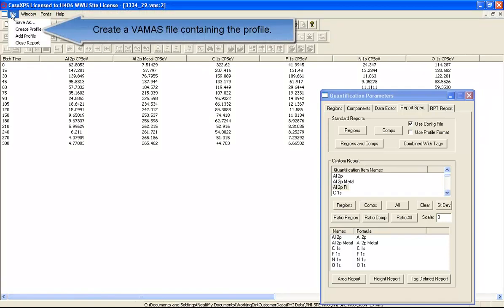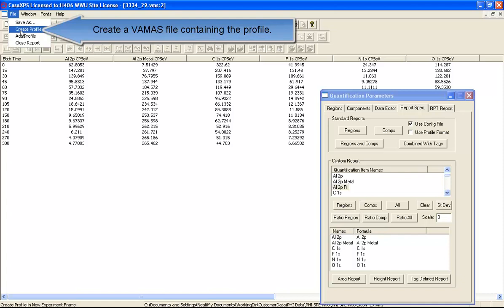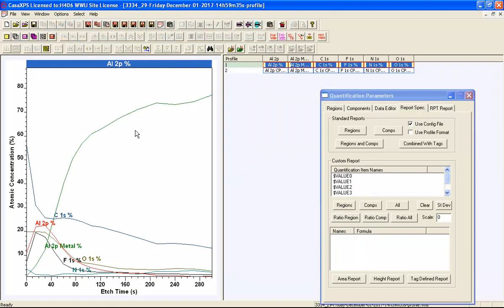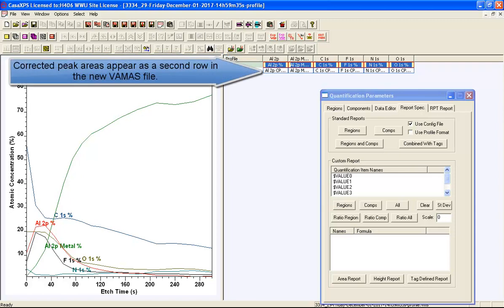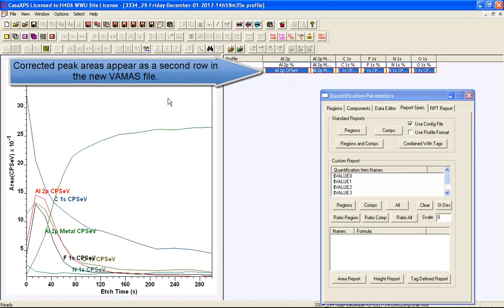To create a profile, go to the file menu and select 'Create Profile.' There is also an 'Add Profile' option, which associates a display with the original spectroscopic file. Selecting 'Create Profile' creates a new VAMAS file containing traces organized from the quantification table. The first row represents atomic concentration as a percentage, and the second row is the profile in terms of counts per second per eV.